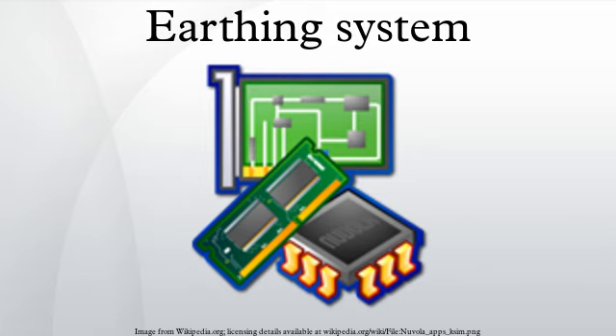The big advantage of the TT earthing system is that it is clear of high and low frequency noises that come through the neutral wire from connected equipment. TT has always been preferable for special applications like telecommunications sites that benefit from the interference-free earthing. Also, TT does not have the risk of a broken neutral. In locations where power is distributed overhead and TT is used, installation earth conductors are not at risk should any overhead distribution conductor be fractured by, say, a fallen tree or branch.